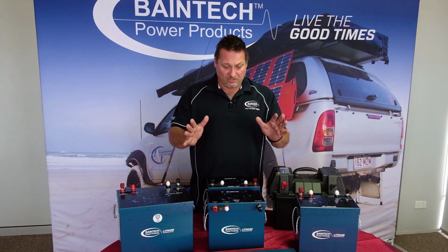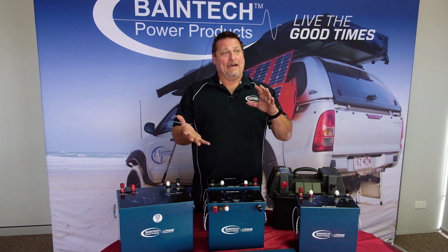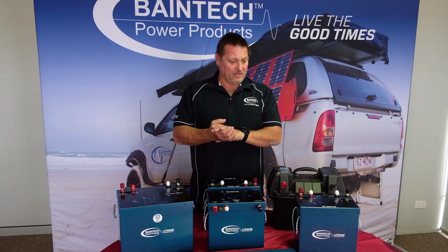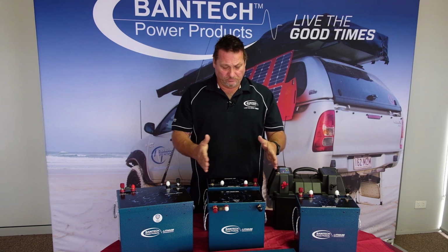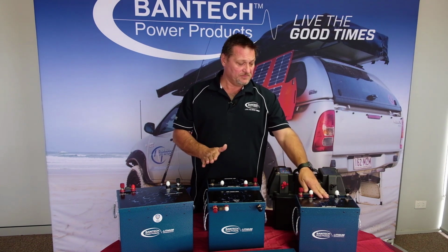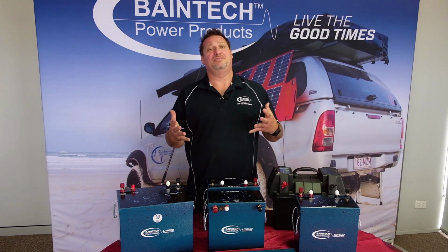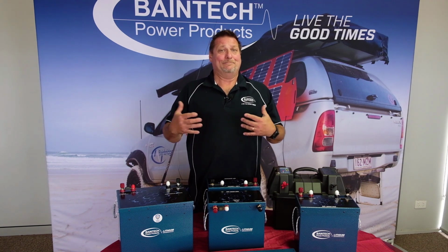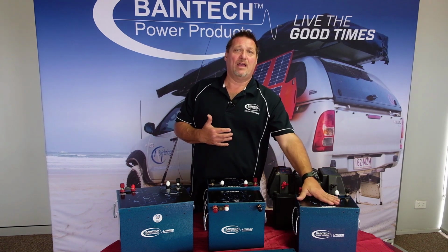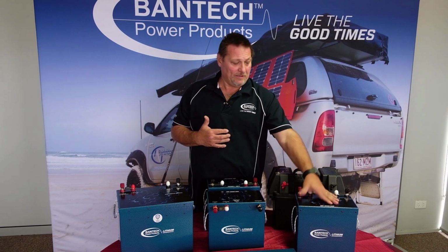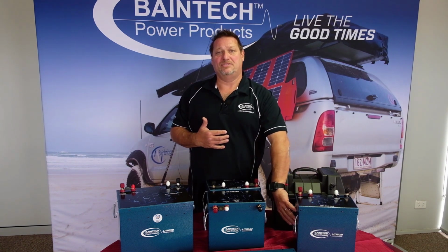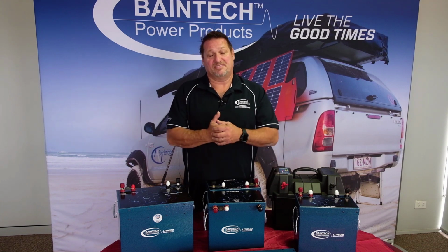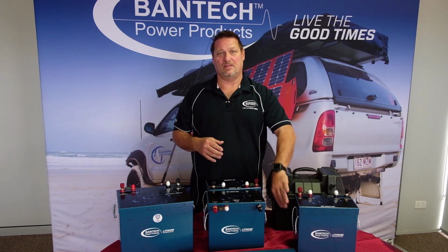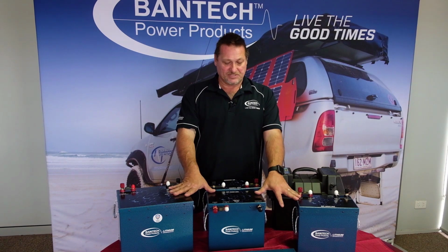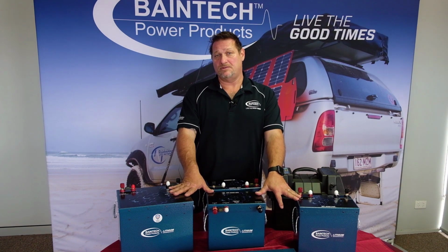I'd also like to announce that we're going to be putting external fuses on these as well. The reason is that if you have a continuous draw, especially through an inverter, pulling more current than the batteries are capable of - rated at 100 amp hour - it will blow the fuse rather than damage the internal BMS. If you get stuck out in the bush, at least you can change the fuse rather than having to get to the BMS.